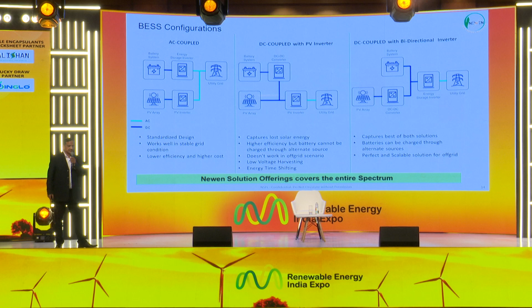The middle option is the DC coupled PV inverter system, where the battery is connected to a DC to DC inverter, and a PV inverter is also connected there, feeding power to the grid. The third option, which is becoming more popular these days because of the higher throughput the system offers, has the battery system and PV array connected through a DC to DC system with an MPPT, then connected to a battery inverter and then to the grid.